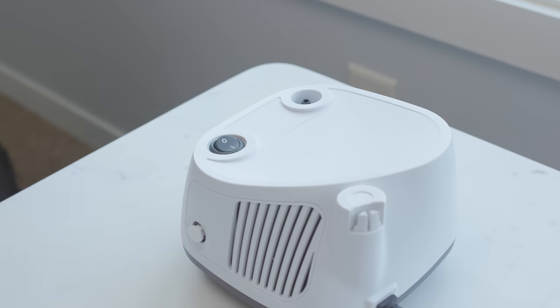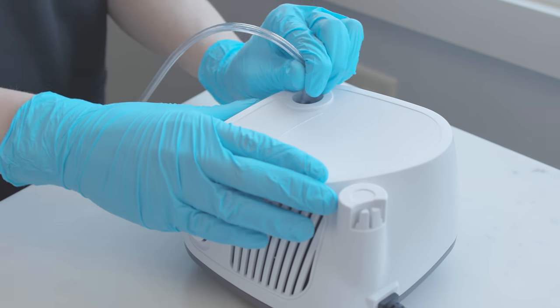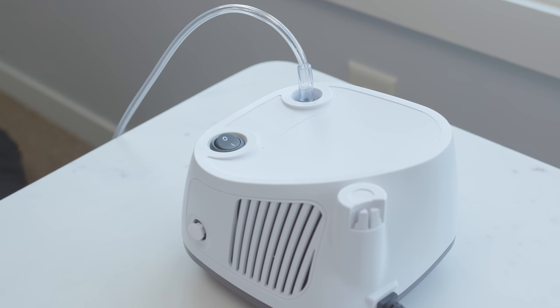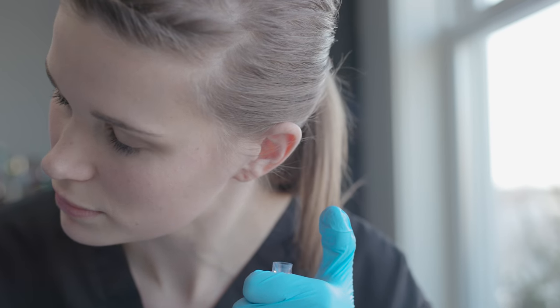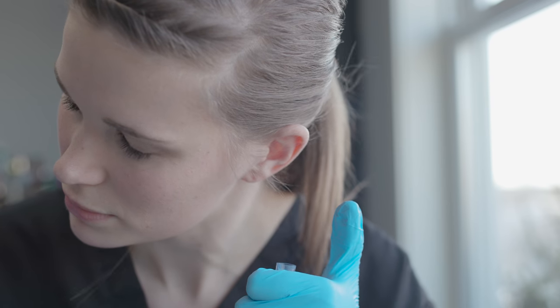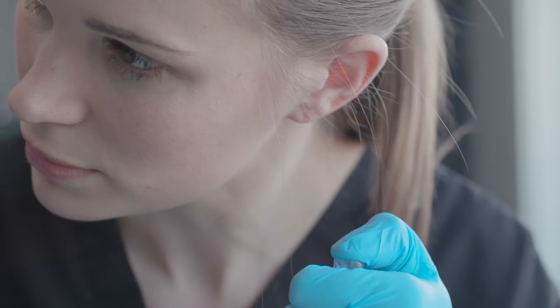If there is a burst of air after checking the machine and filter, attach the neb tubing to the neb machine. Put your finger over the open end of the neb tubing. Remove your finger and listen and feel for a burst of air.